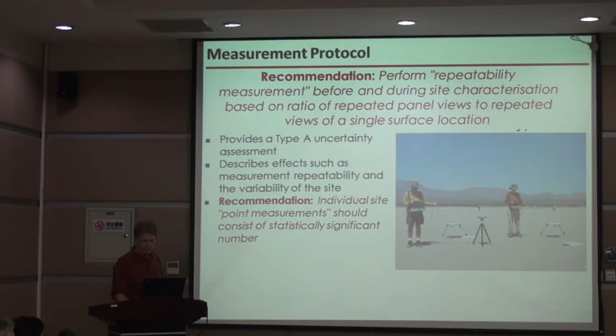Perform repeatability measurements. This was prior to us implementing the gray panel, but the gray panel was implemented because we were trying to assess these types of instrument measurement uncertainties. And this came out of the Tuscaloosa work as well: not only do you want to have measurements of your white reference for a reflectance calibration, but you want to have measurements of something else that allows you to assess how much your instrumentation is changing over short time periods. What's the noise of your instrument?